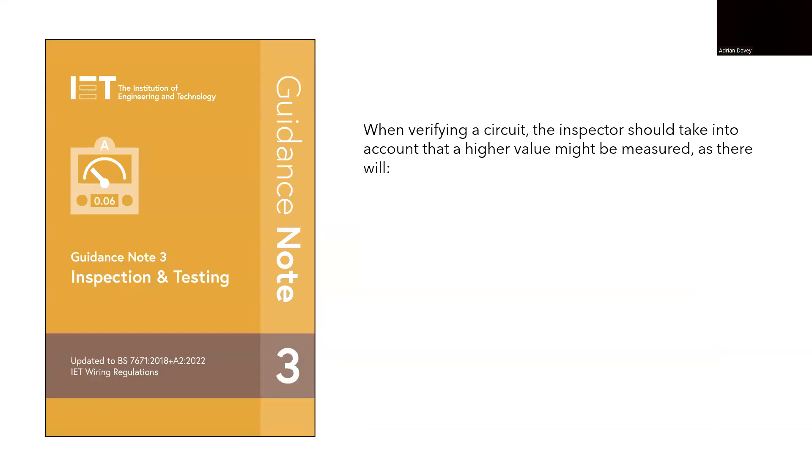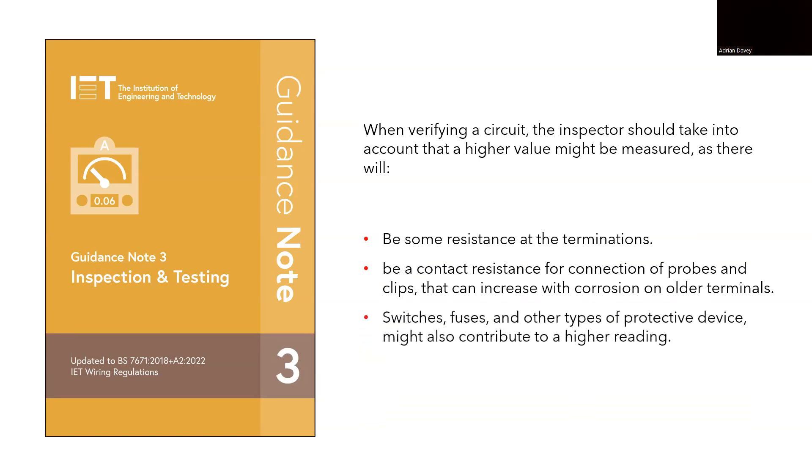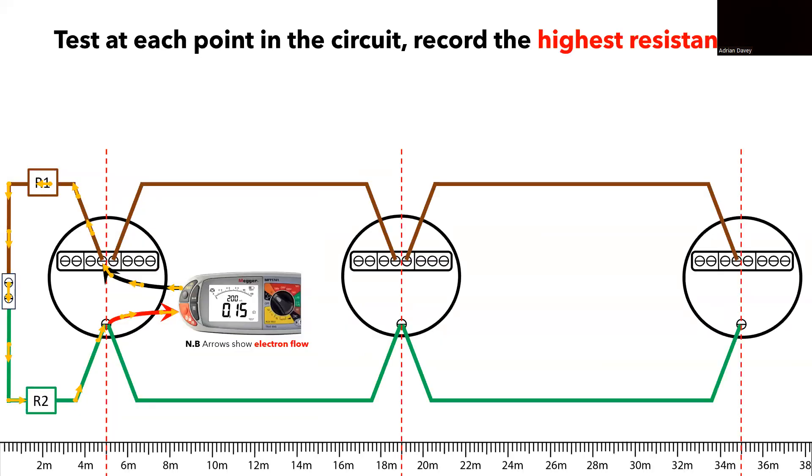The IET's guidance note 3 is another book I recommend purchasing if you are involved in inspecting and testing electrical installations. Since we might obtain a value higher on our MFT than the calculated value, it offers the following guidance. The inspector should consider potential higher measured values as a result from resistances at the termination within the circuit, contact resistance on the test probes from the MFT, and the presence of switches, fuses and other elements within the circuit that are not part of the cable. Since the value we measured in our MFT closely matches or is similar to what we calculated, we can conclude that our circuit is well connected at this point and utilizes the appropriate cable size.